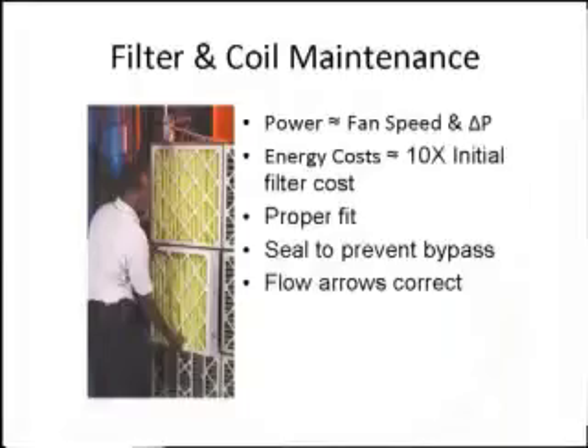You're going to use. So as these clean filters, they've got a certain differential pressure that they're rated at as they come from the manufacturer. As they begin to get dirtier and dirtier, this goes up maybe by as much as 20–25%, and that translates linearly into a 20–25% increase in power. So both of those things we're going to look at a little bit, and beyond the filters, I mean the coil is the same thing. It's obviously important to keep it clean.